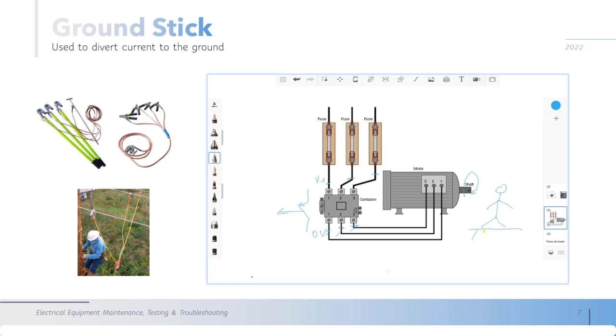and you are also on the floor and the floor is ground. You are working here in this phase. For some reason someone closes this contactor or the control circuit fails and this contactor closes. This voltage will be applied here, so you will have a voltage difference from 0. So the motor will start running and you are touching this phase, so that means a voltage will be applied to your body or hand.